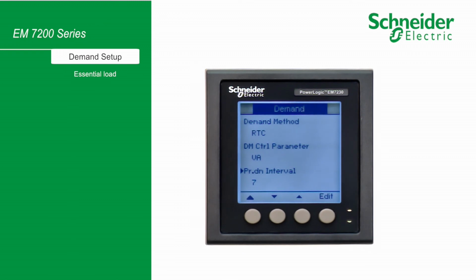This innovative feature enables you to exclude some of the essential loads from the demand controlling option. That means demand is calculated for entire connected load in the system, but computation for controlling technique does not include the essential load factor. If you are unsure about the essential load factor, we recommend you to set the value to 0 or near to 0.